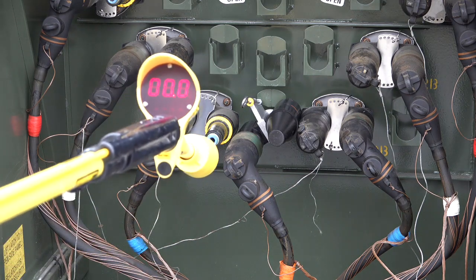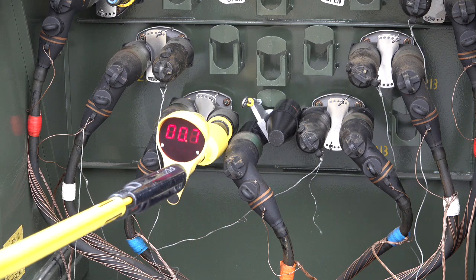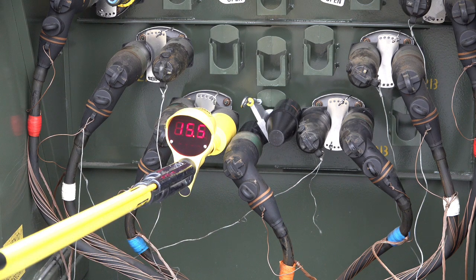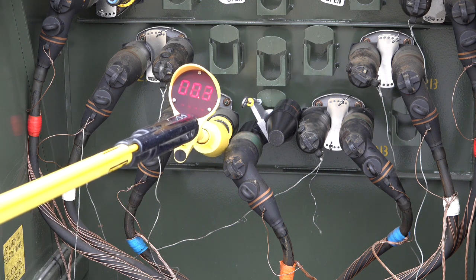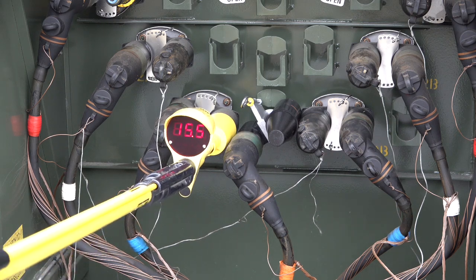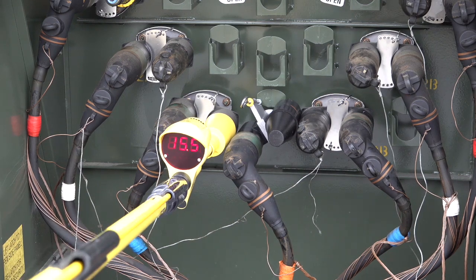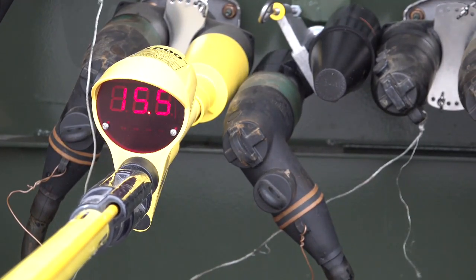So now, if we insert our VD1000 into the bushing of the pad mount transformer, the voltage displayed is a nominal voltage. All single probe voltage detectors can only display a nominal voltage. In order to achieve a nominal voltage reading, a voltage detector must capacitively couple to its environment. Many variables can adversely affect the reading of a voltage detector, and these would include temperature, humidity, or proximity to ground planes or other voltage potentials, high or low. If we remember, the PD25 displayed 14 kV true RMS voltage. If we compare that to the VD1000 at 15,500, we'll realize that that is accurate within 10%. This far exceeds the accuracy requirement in ASTM F1796 of plus or minus 30%.